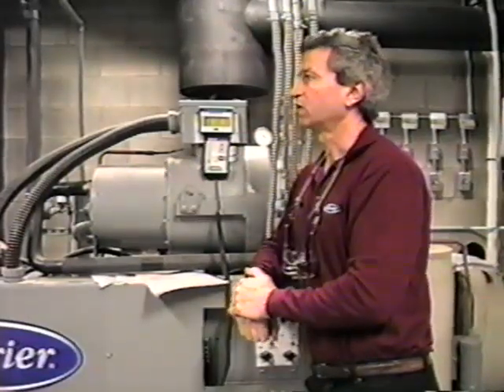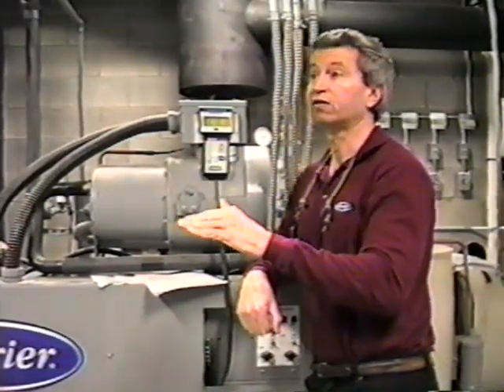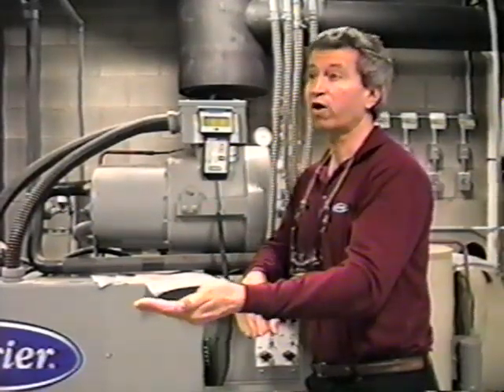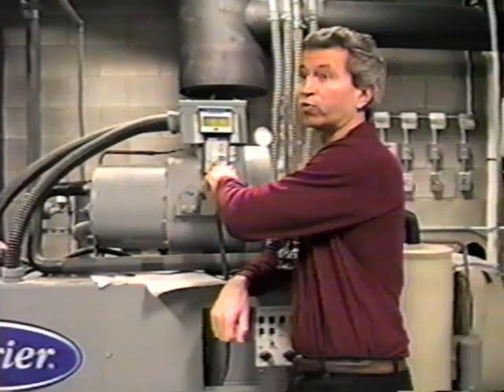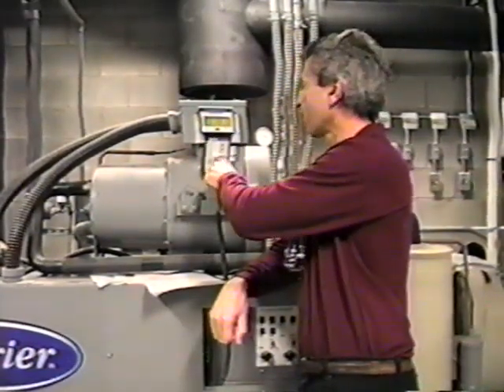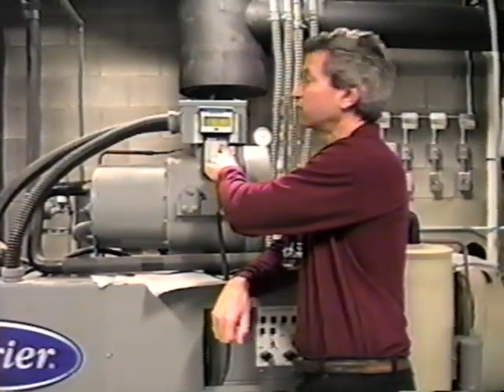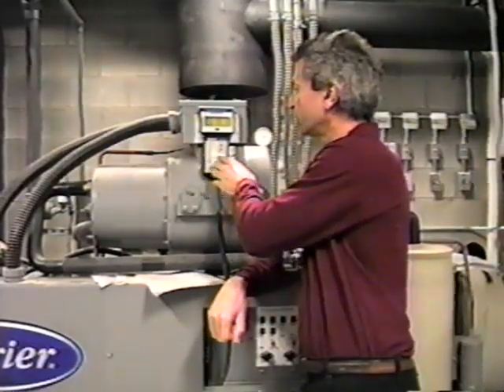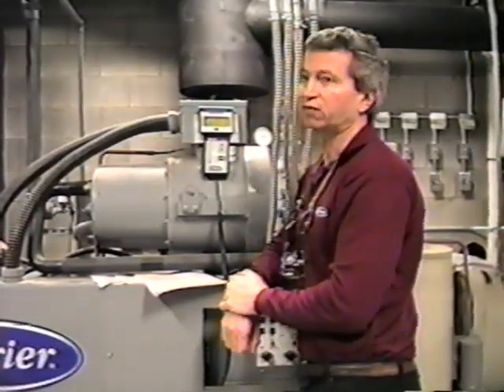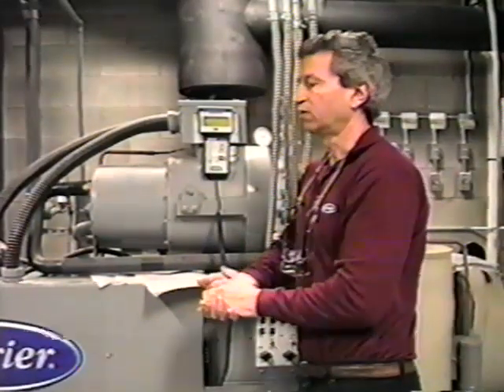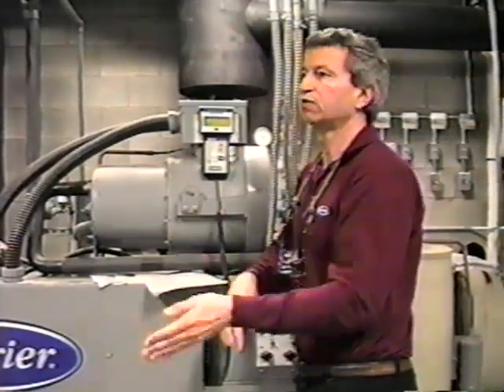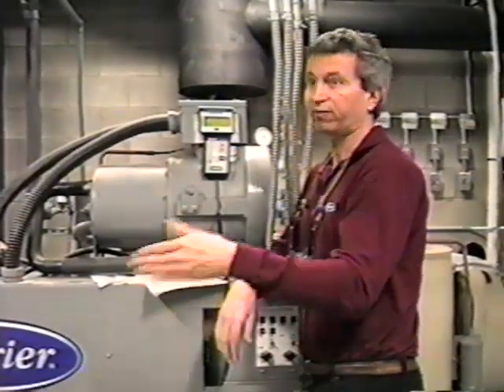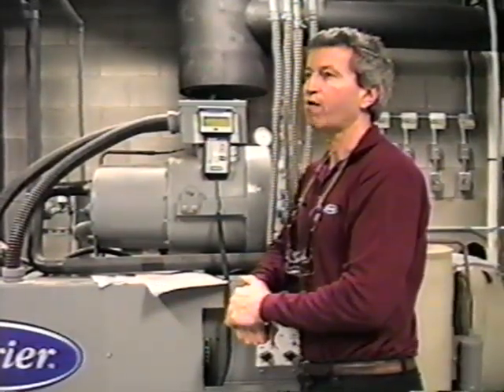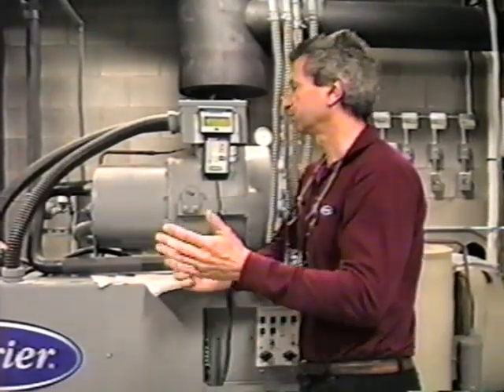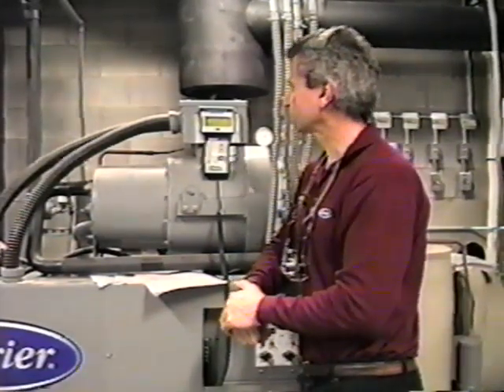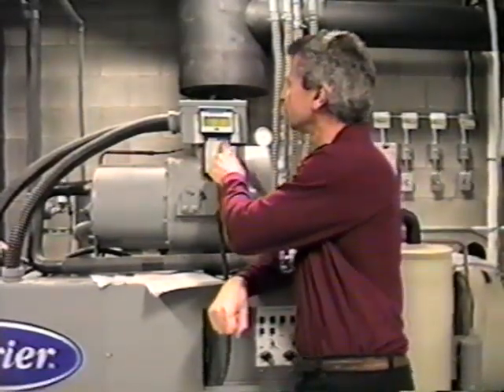One of the lines on the default screen is override mode in effect, yes or no. Okay, and then if you wanted to know what override mode is in effect, you can go to this screen, operating modes, and scroll down, and that particular mode will be on when it tells you an override mode is in effect. So again, they're listed by numbers if you wanted to know what they are. Timed override in effect. You won't see that because we don't have any time clock between stop and start, but we can program like a 15-minute stop to start time clock in there. There's no need to do that here because we don't see any chance of it short cycling. But if that were in there, that's one of the modes you could see.